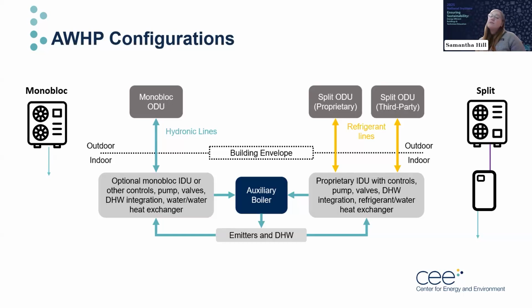For split systems, they have refrigerant lines that enter into the building, and it's in the indoor unit that the refrigerant to water heat exchanger lives. And that then interfaces with any kind of distribution you might want. You can add auxiliary heat sources, you can add different types of emitters, and you can add different types of loads like space conditioning or hot water to either of these systems. And they're just essentially two different styles of the same sort of technology. The benefit of the monoblock system is that you don't need to do refrigerant charging in the field. That can all be done in a manufacturing setting. And the connection to the home is really all water lines, which requires a different skill set than doing refrigerant work, which is still required for our split systems.